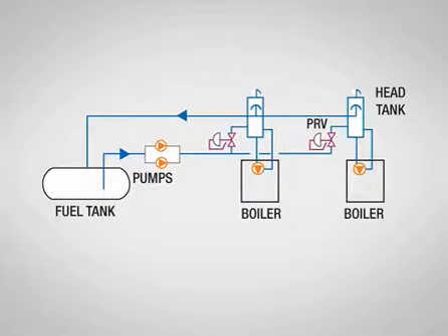Boilers commonly have onboard positive displacement pumps to boost the pressure from the recirculating loop and provide a high-pressure, uniform supply. A second means of supplying a high-pressure supply is to use a day tank that is refilled from the main storage tank. A higher-pressure duplex pump set draws from the day tank to make a mini recirculating loop within the boiler room.